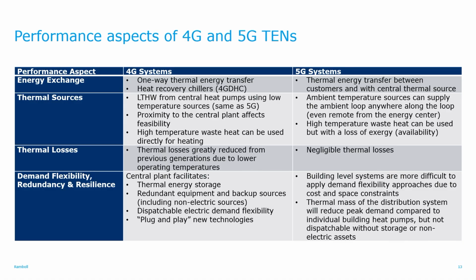A central plant in a 4G system facilitates some features that give it demand flexibility, redundancy, and resilience. Since it's centralized equipment, you can easily accommodate thermal energy storage, chilled water or hot water or both. Also, it's easy to install redundant equipment and backup sources, which could include non-electric sources for resiliency or potentially for demand flexibility.